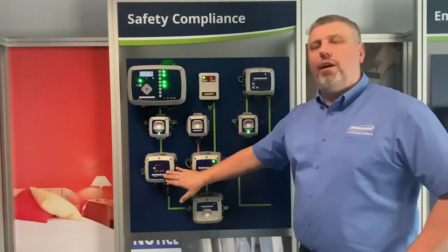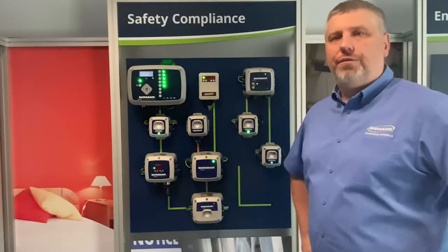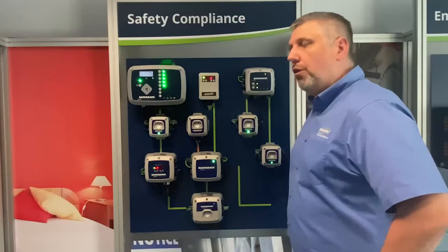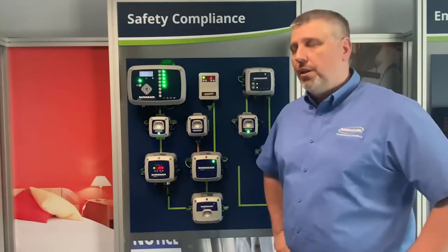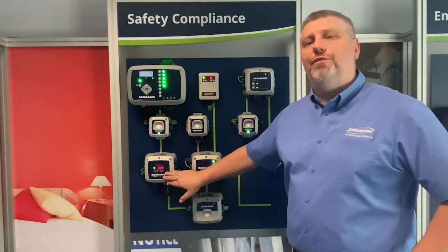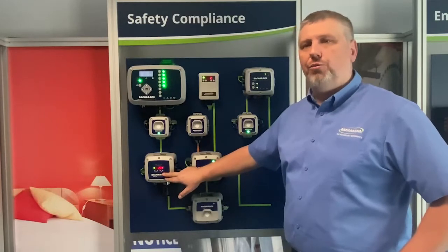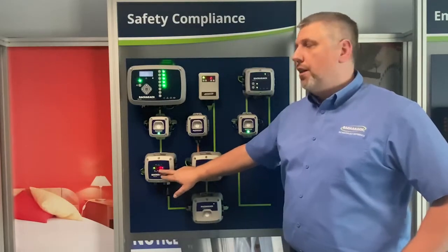The MGS 550 line of gas detection sensors from Bacharach utilises all the features of legacy products. It supports multiple sensors and multiple sensor technologies, including semiconductor sensors, electrochemicals, infrareds, and catalytic sensors for high concentrations of hydrocarbons. The unit communicates using audiovisual signals and has a display allowing the customer to see the actual ppm range and gas concentration.